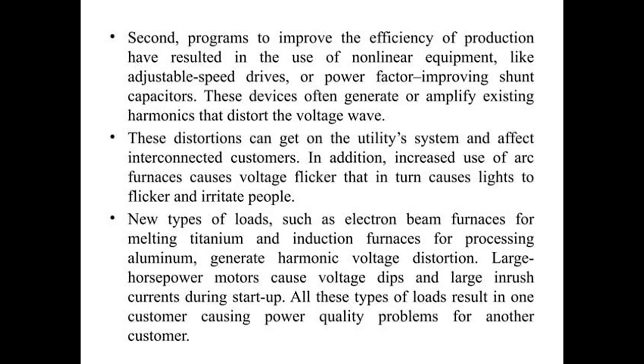New types of loads such as electron beam furnaces for melting titanium and induction furnaces for processing aluminum generate harmonic voltage distortion. There are many cases where we use large horsepower motors - induction furnaces included - causing voltage dips and large inrush current during startup. If you take any motor, such as a DC motor or induction motor, initially when starting, the current taken by the motor is more - we call this inrush current. If the inrush current taken by the motor is high, you ultimately get voltage dips, or in simple words, voltage sag.